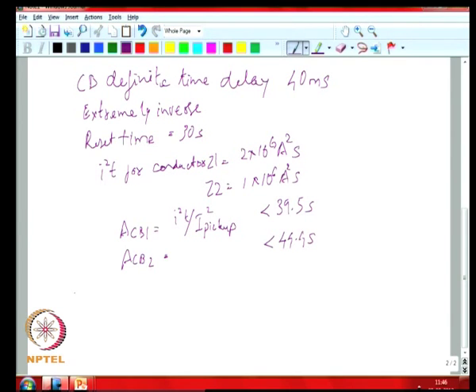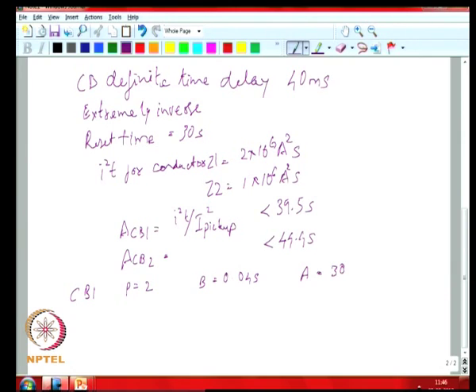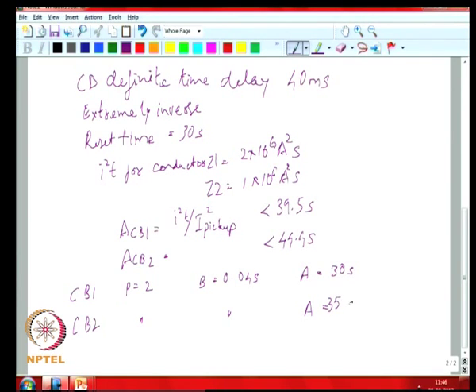We decided to have breakers CB1 and CB2 with P equal to 2, B equal to 0.04 seconds, and A equal to 30 seconds for CB1, which is less than 39.5. For CB2, P and B are the same, and A is selected as 35 seconds, which is less than 44.